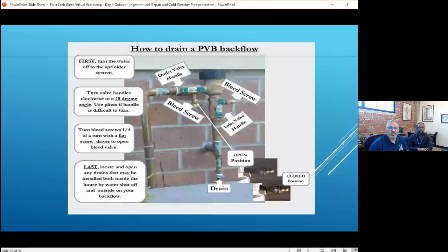Always turn the water off. If the valves get stuck, you can use pliers to help turn them, at a 45-degree angle. Then take a flathead screwdriver to the test ports, indicated there in the open position, the bleed screw. Open that a quarter turn to allow the water to drain out through the test port.